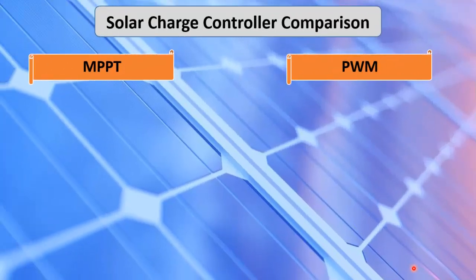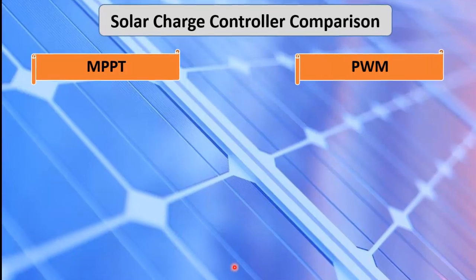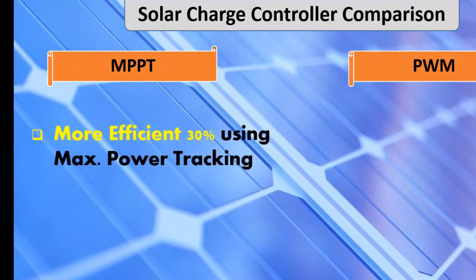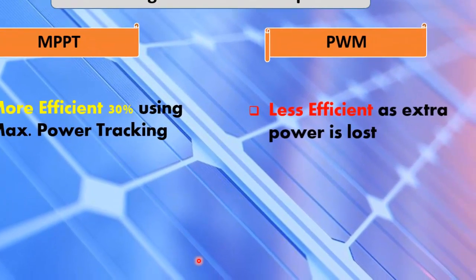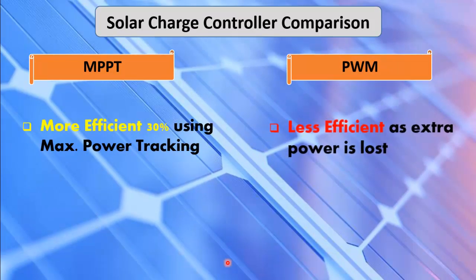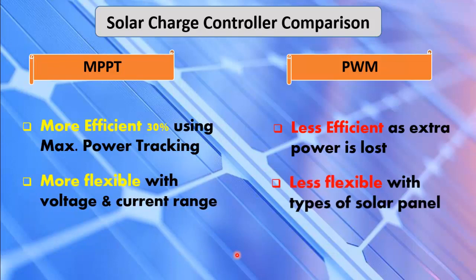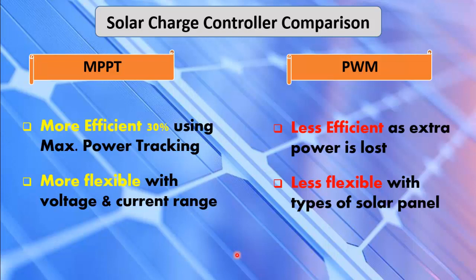Let's quickly compare MPPT and PWM solar controllers. As seen previously, MPPT is 30 percent more efficient in terms of power conversion, whereas PWM is less efficient as extra power is lost. MPPT is compatible with a wide range of solar panels because it can convert voltage and current according to the load. PWM controller is less flexible as it must be selected carefully according to the battery voltage. MPPT is more expensive than PWM, but it can quickly recover its price because of higher efficiency.